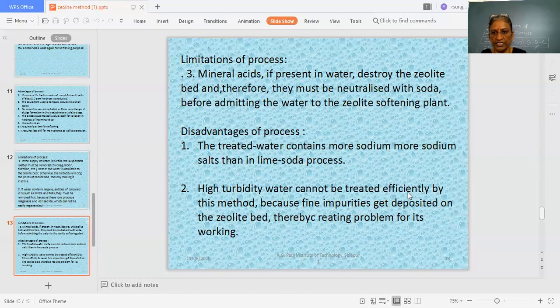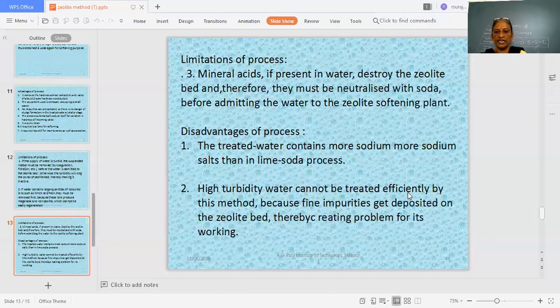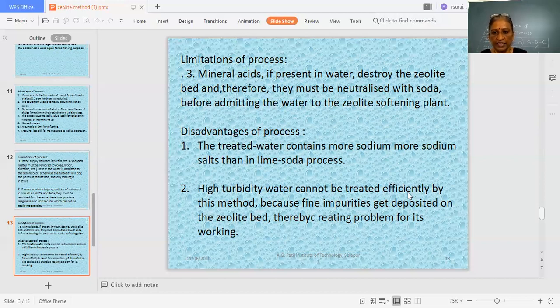A third limitation is that mineral acids, if present in the water, destroy the zeolite bed. Since zeolite is basic in nature, when it comes in contact with acid it neutralizes the sodium and the exchange property is reduced, so acidic water cannot be treated in a zeolite bed. High turbidity water also cannot be treated.